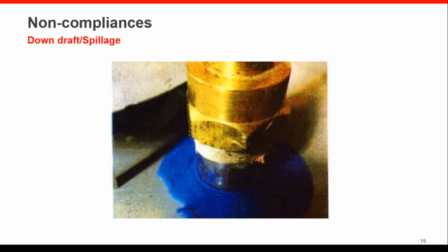And this first one is somewhat subtle, and you really could miss it. But what I want to draw your attention to is that this is an indication of a possible problem. If you note the melted blue grommet in the picture just below, that's a draft hood off of an appliance, I think probably a water heater.